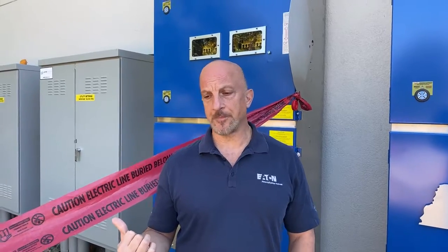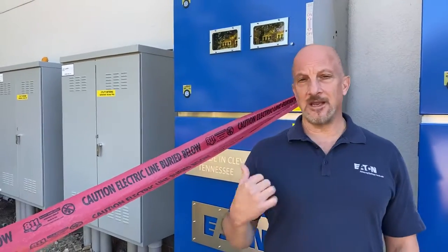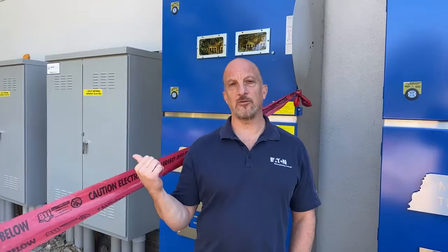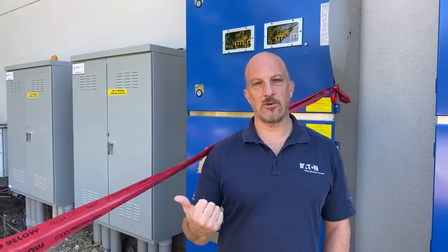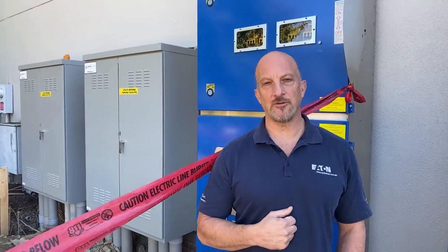So that's for the PSEC part and the new energy aware part with the switchboards. The next move will be to put in two Eaton transformers out here in the spring, and then we'll bring in the medium voltage to a disconnect that's a breaker or some sort of medium voltage switchgear, go to our two new transformers, and take medium voltage service for the building.